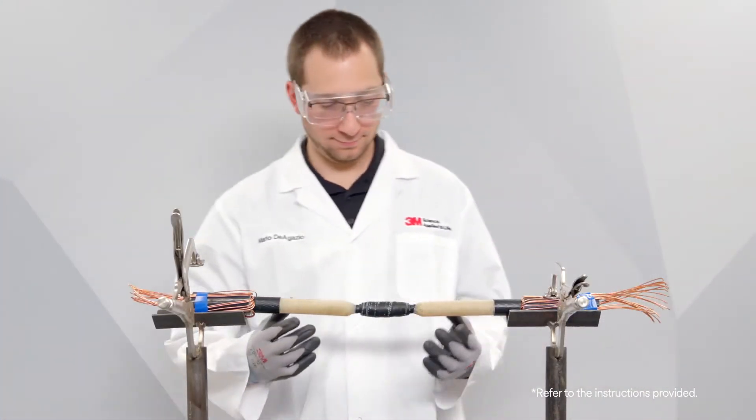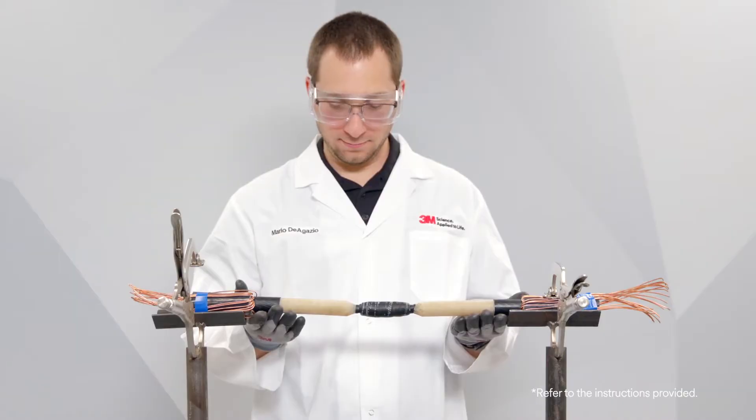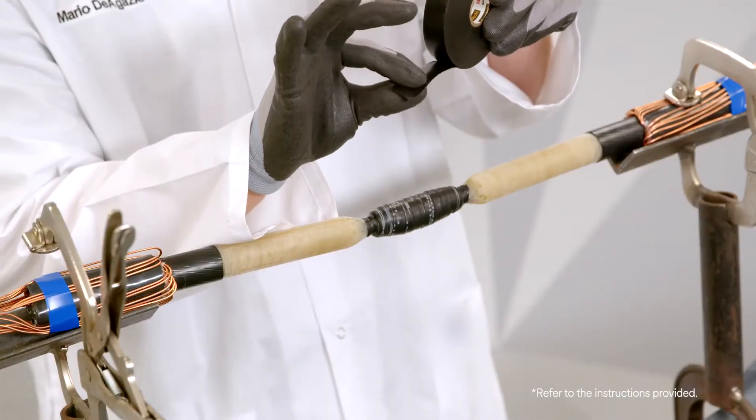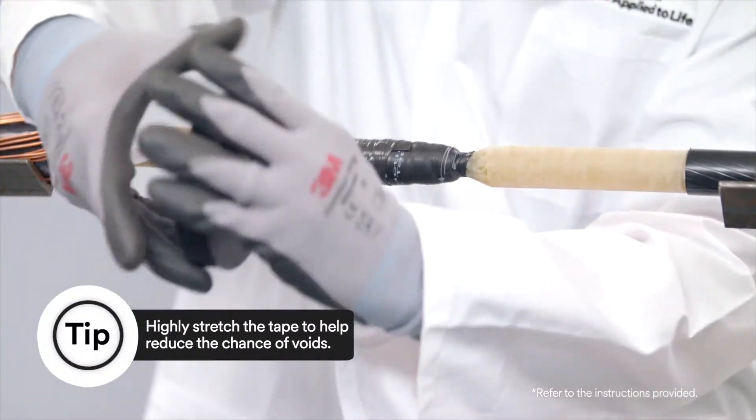Prepare cable as per standard practice. Apply Scotch Linerless Rubber Splicing Tape 130C tacky side up using highly stretched half-lapped layers.